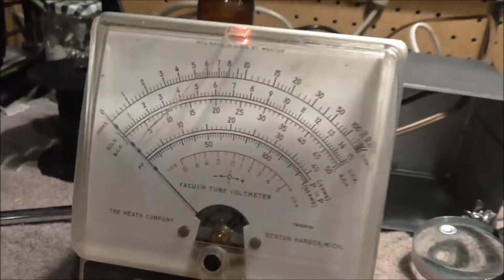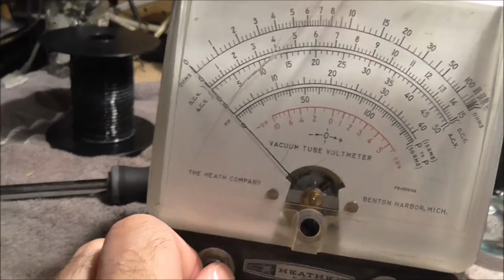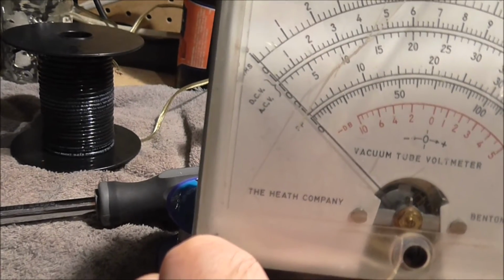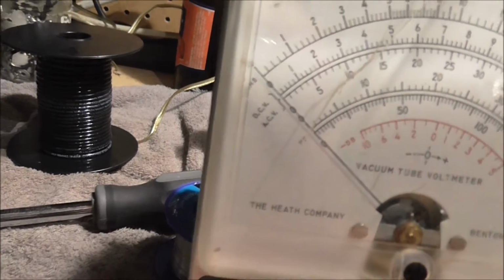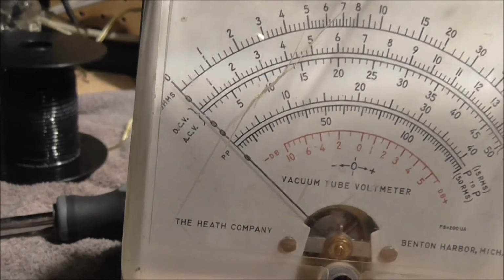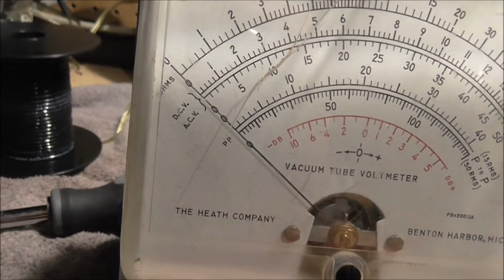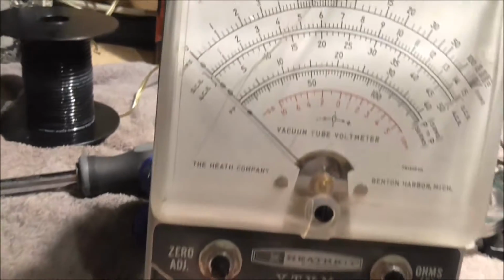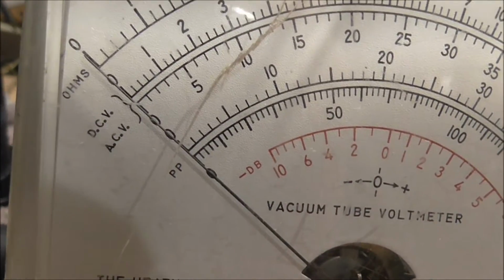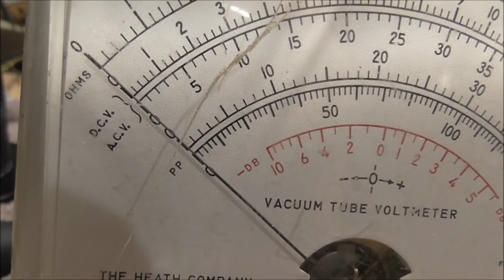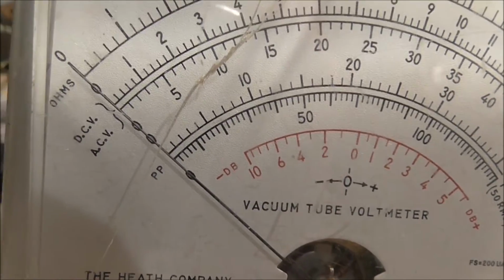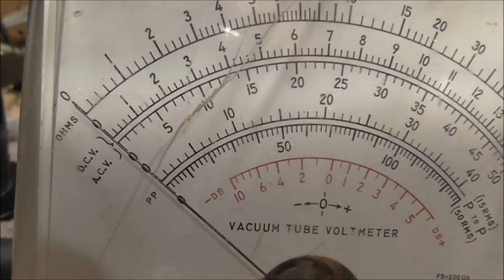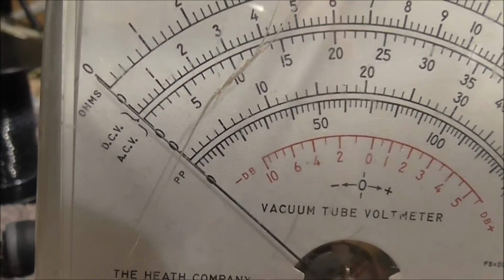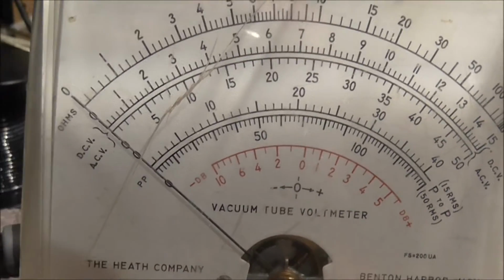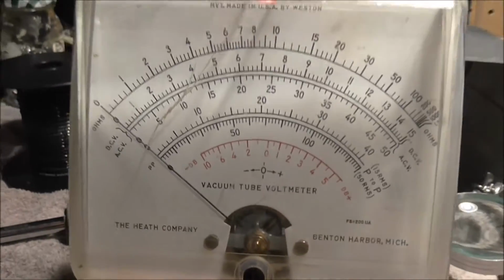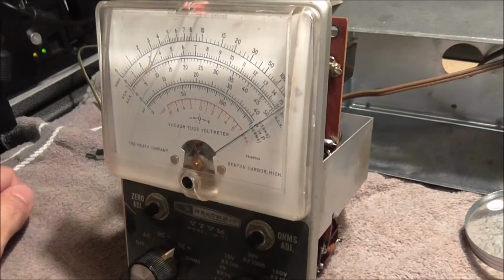Alright, so I've let it warm up sufficiently, and so now I'm doing the DC, or the 0 adjustment, which is done on DC plus. There it is. And in theory, you're supposed to be able to switch to DC minus, which I've done, and AC, and have the line remain very close to 0. As you can see, it's nearly perfect. And the only movement of the needle is really because I'm slightly touching the meter itself, not because of any problem. So that's good. Alright, so I'm in DC plus. I'm going to hook up to a battery and calibrate that.